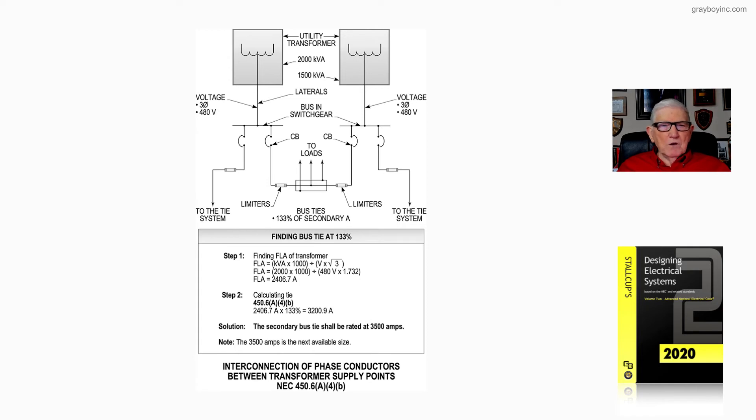We find the full load amps of the transformer. KVA times 1,000 divided by the voltage times the square root of 3. So we have 2,000 times 1,000 divided by 480 times the square root of 3, 1.732. When we do the math, we come up with 2,406.7 amps.